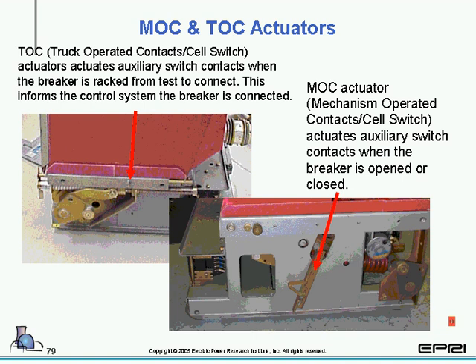We have mech and truck actuators. Now, truck actuators actually stand for truck operated contacts. And what these do, as the breaker is being racked from the test to the connect position, they let the system know that there is a breaker in the connect position and ready for use. The mech actuated contacts change state when the breaker opens and closes. So the truck operated contacts, or TOC, operate when the breaker is being racked. Mech actuated contacts operate when the breaker changes state from closed to open and then open to closed.